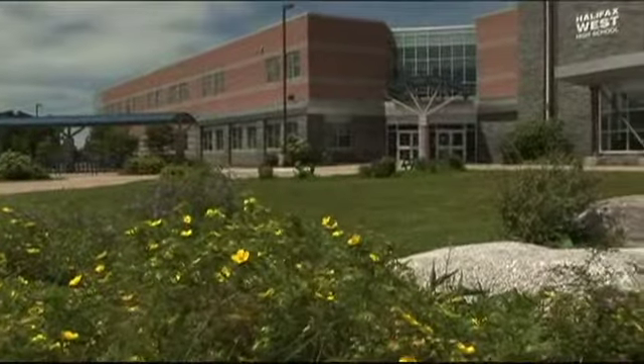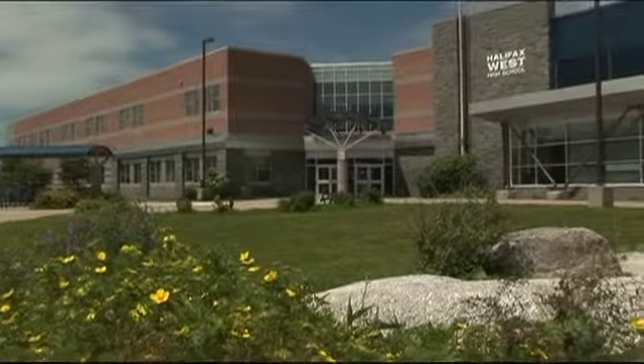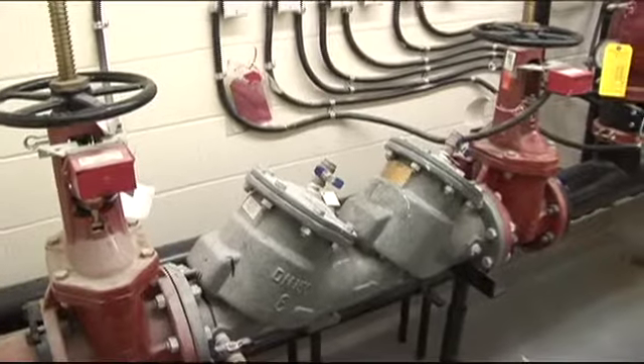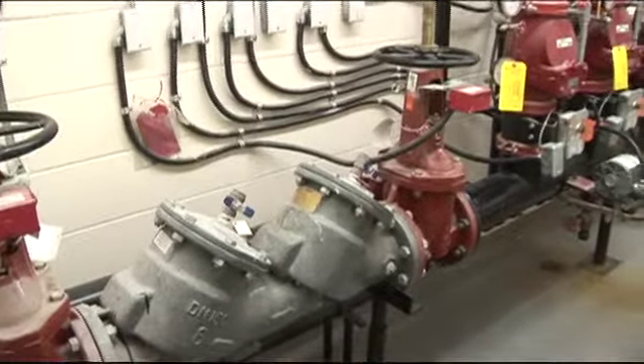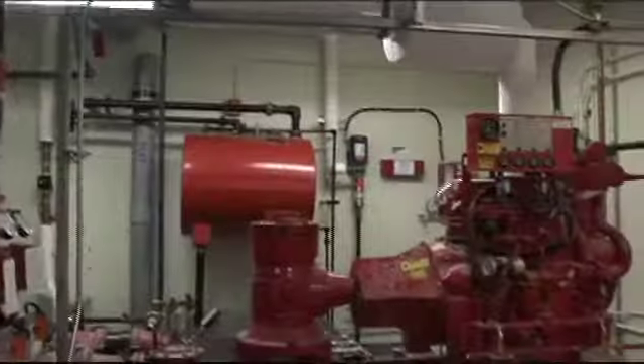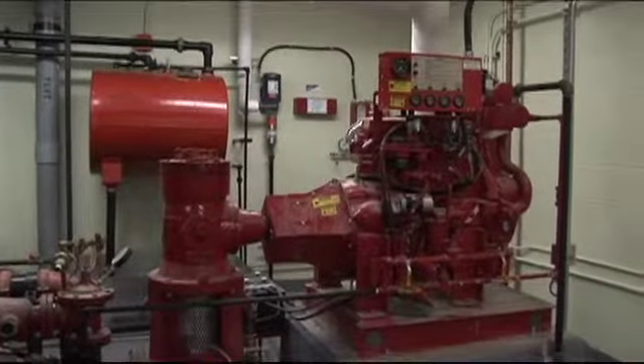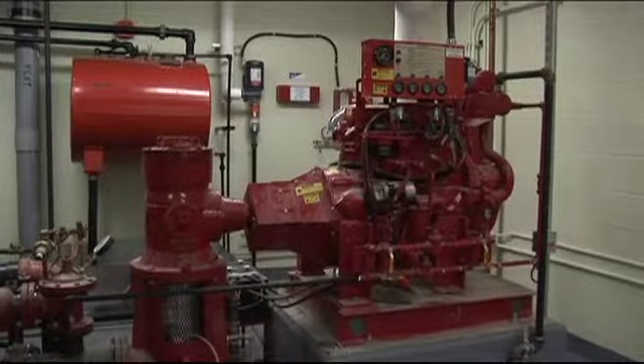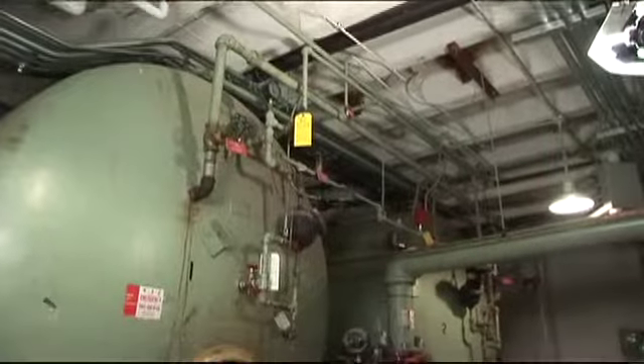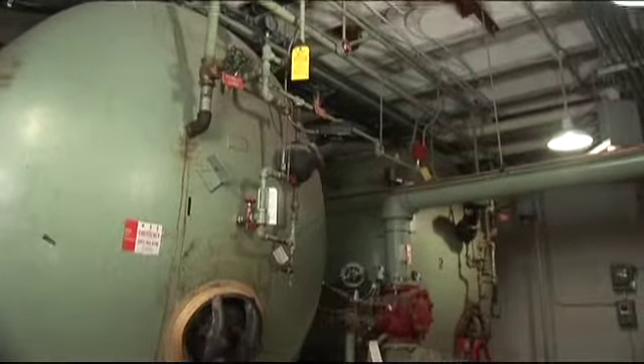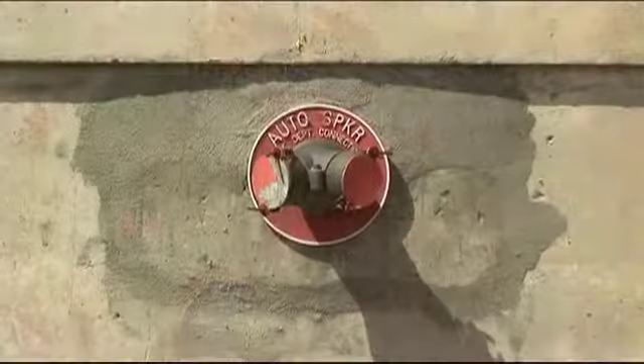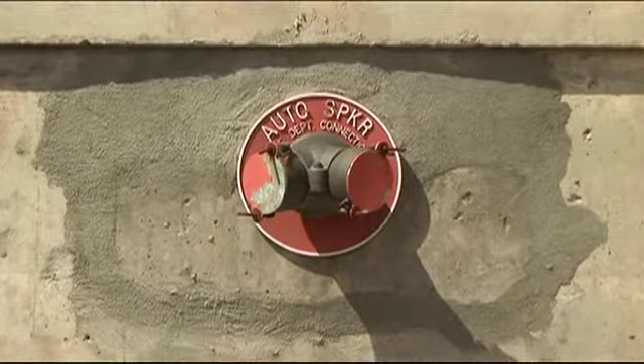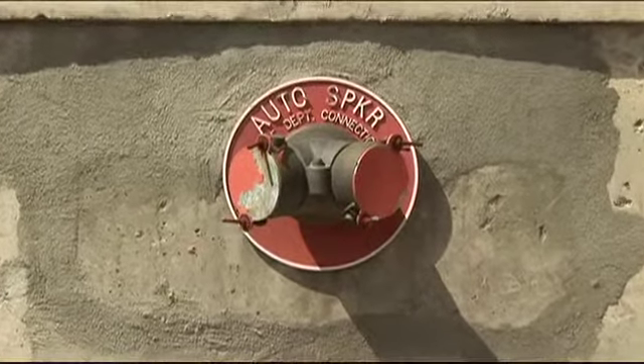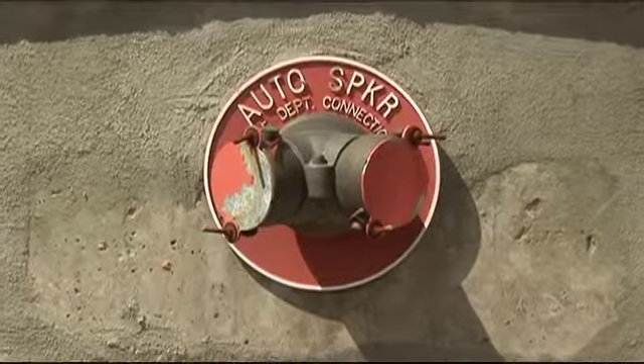Sprinkler water supplies are usually fed from the main water entrance for the building. Some systems in larger communities and cities that are on municipal supplies or have their own reservoir may require an electric or diesel fire pump to generate the correct water pressure. However, some schools may require the use of pressurized water tanks. The sprinkler system can also be boosted by a fire department pumper truck via the fire department connection located outside of the facility.